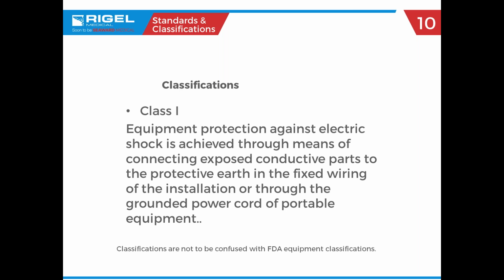Let's talk about the different classifications out there. When it comes to electrical safety testing, a class 1 device is equipment that has protection against electric shock, achieved by connecting exposed conductive parts to the protective earth in the fixed wiring of the installation, or through the grounded power cord of portable equipment. That was a very long-winded definition, but basically just a device that has a ground pin on the power cord - that's the easiest way to think of it.